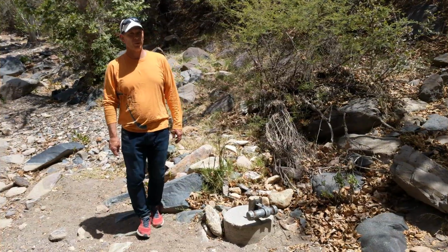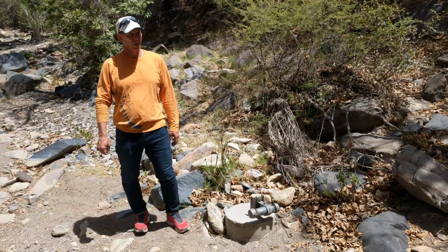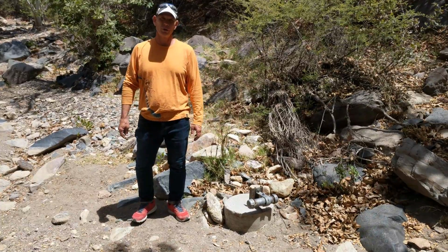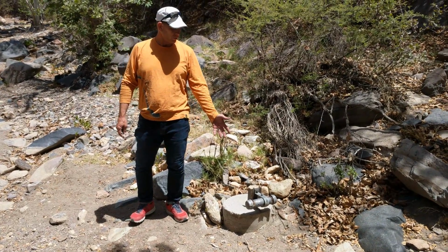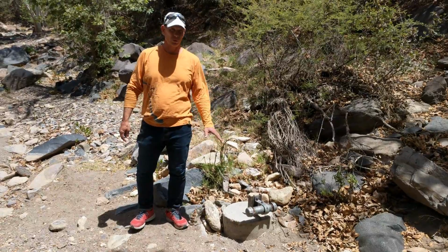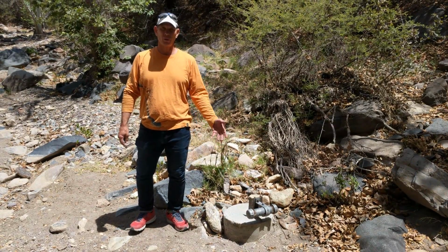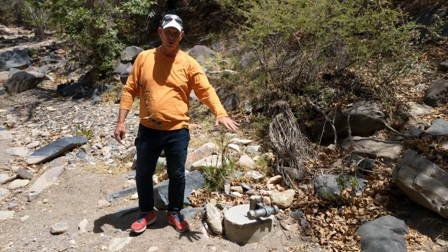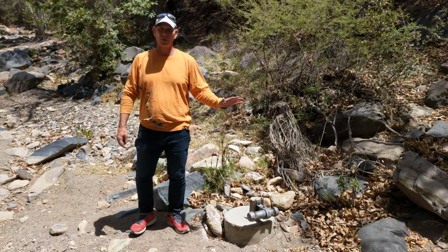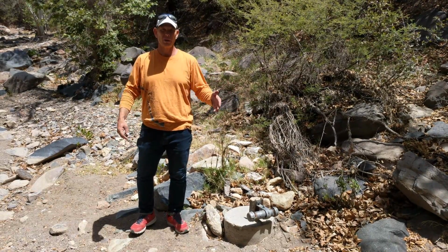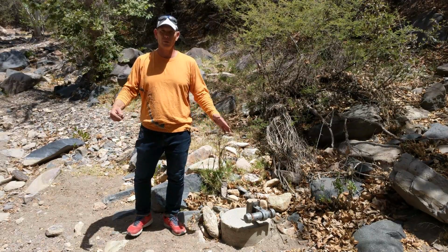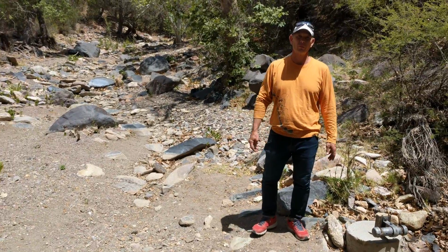Part of Sycamore Creek, we're working with the U.S. Geological Survey, and they've installed what they call a continuous slope area reach, or CSA. At this location that involves a data logger, which is low to the ground, and it consists of a pressure transducer as well, which will record the level as it rises and falls. They have to come back and download this data and take it back to analyze it. But this gives us a continuous slope area, continuous discharge of what's going on here, so that we can figure that out after the event.